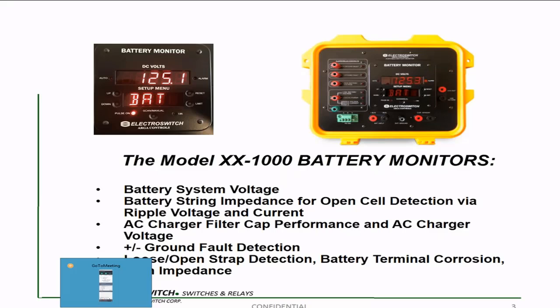So I'm going to present information associated with the 1000 battery monitor system. I have it identified as XX1000 because, depending on whether you want a panel or a portable unit or a rack-mounted unit, there's a different designation in the front. So what this does is our battery monitor system. It monitors battery system voltage. It's monitoring the battery string, not individual cell voltages.